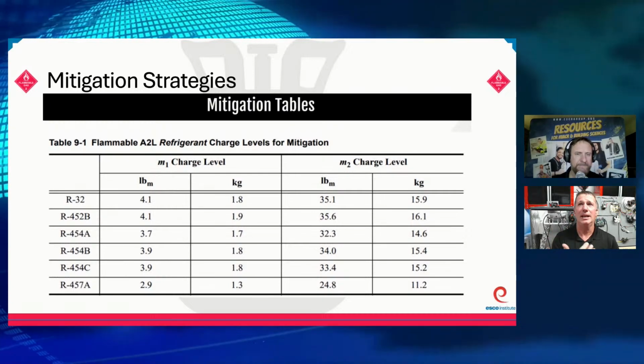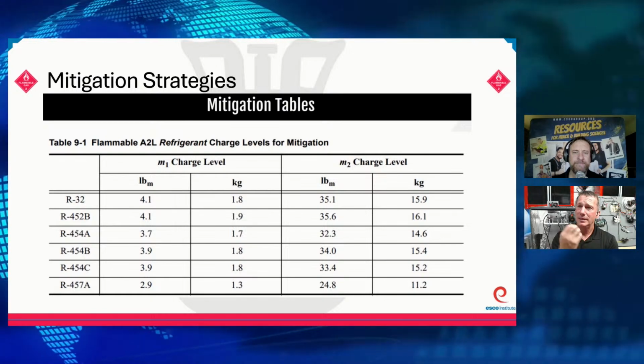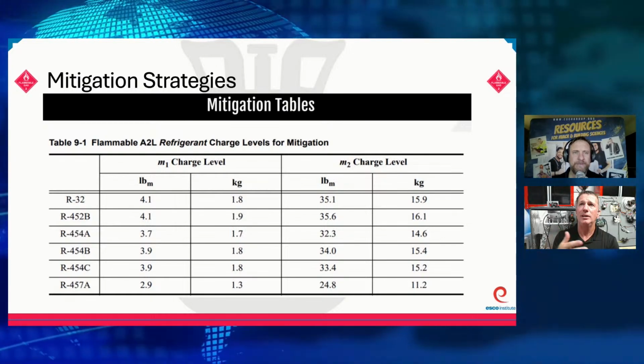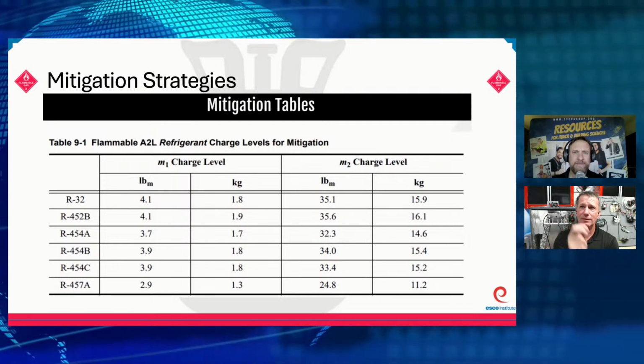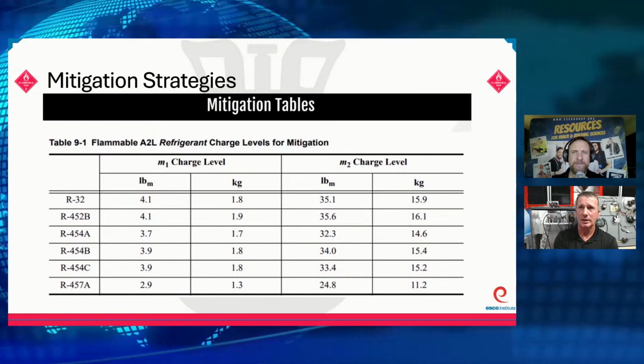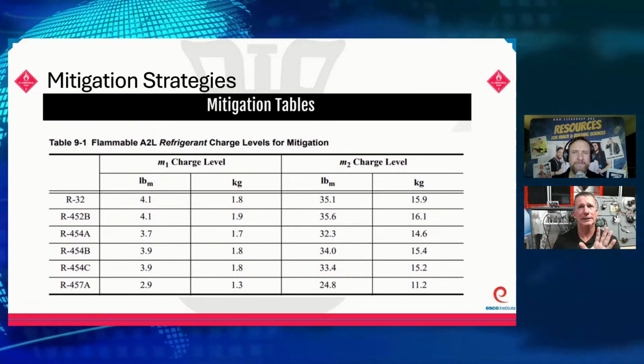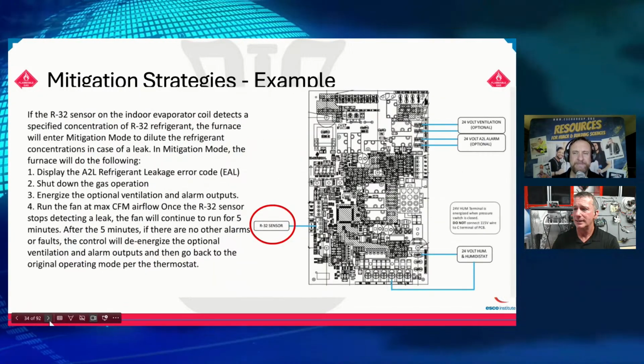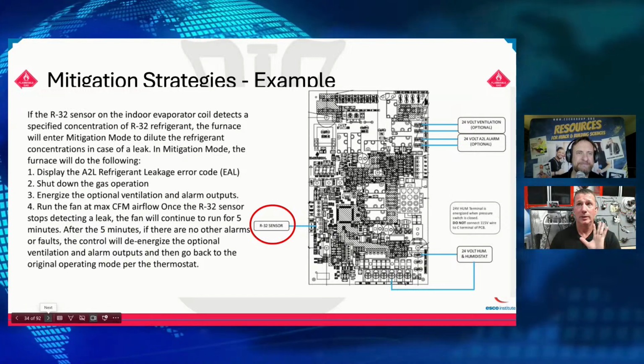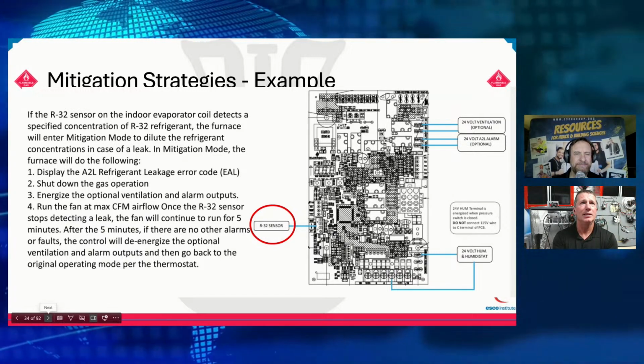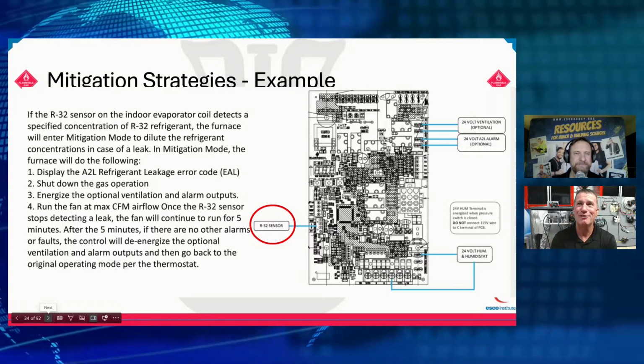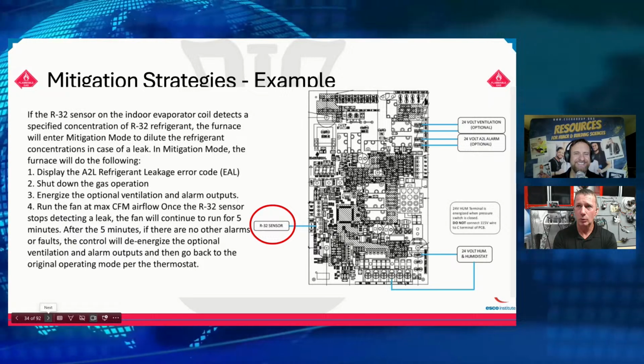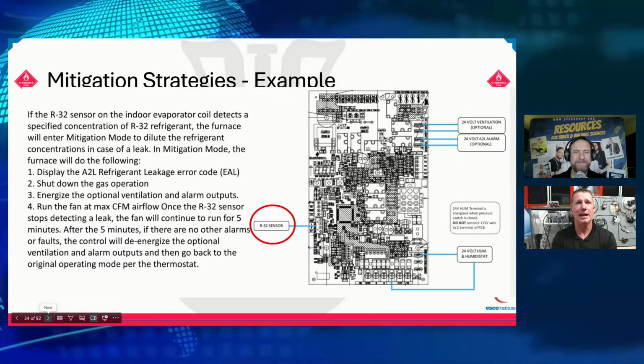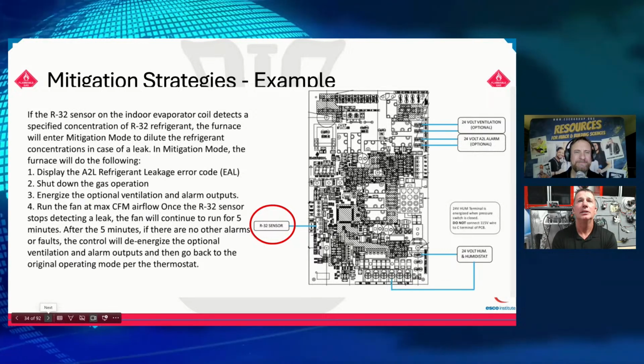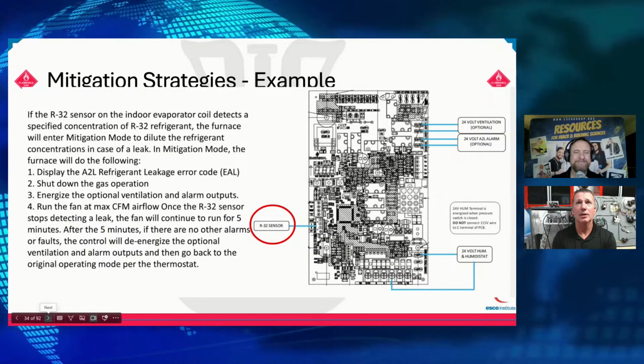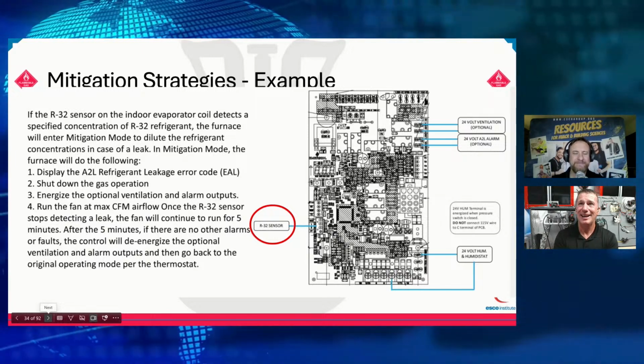Now, when we get into our communicating systems, we're already going to have these connections built into them. And as we continue moving, all of our furnaces and indoor boards will eventually have the 4-pin connector already established on it. So we're going to have this little intermediate window where we will be utilizing these controls, because I can say that we absolutely will be doing that, because this is an installation manual for this major manufacturer on one of their 80% furnaces that will be hitting the market. And you can see that it already has the R32 sensor, the 4-pin connector, landed on the factory furnace control board. And they also did our optional contacts, 2 of them.